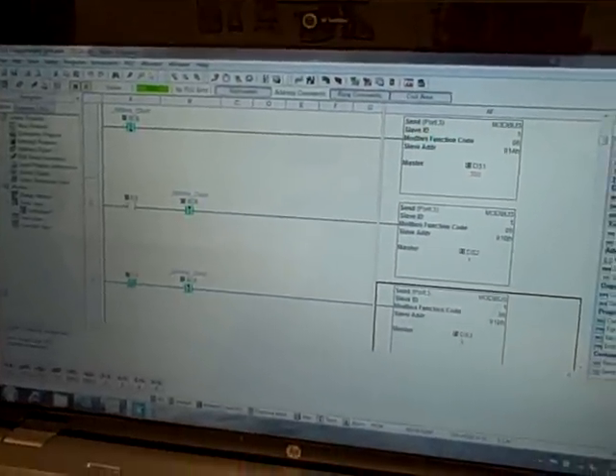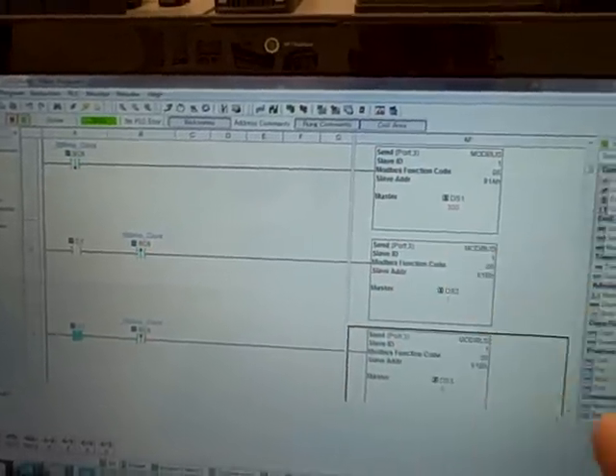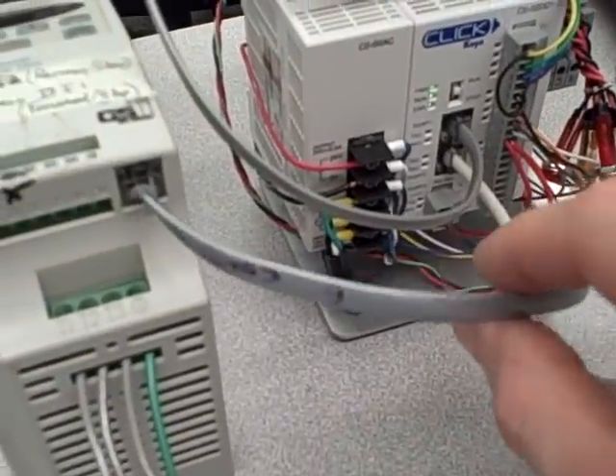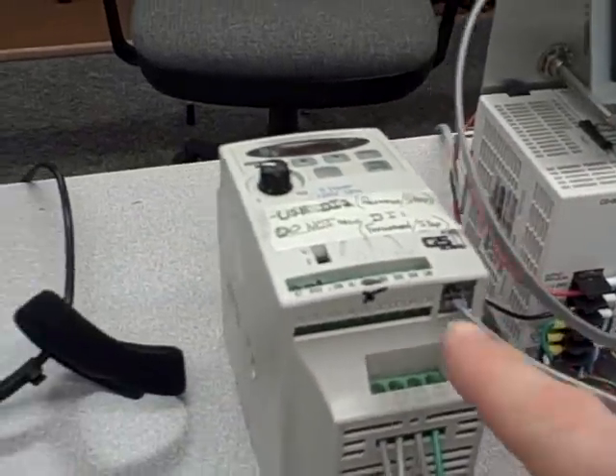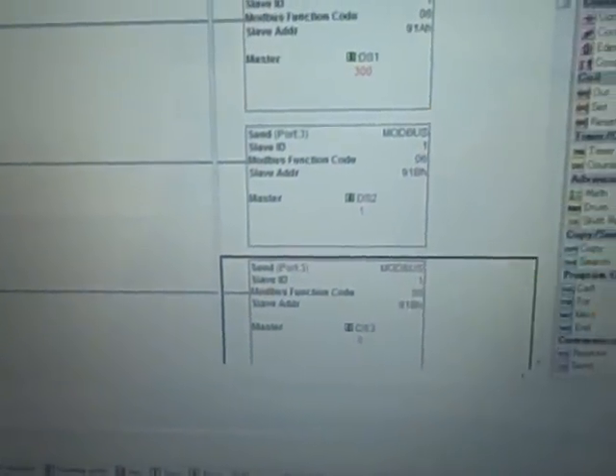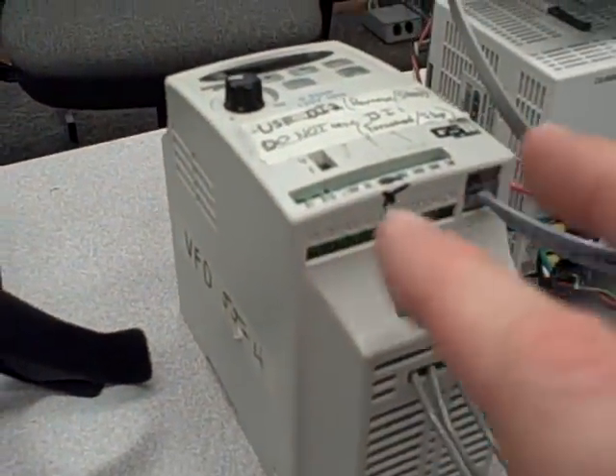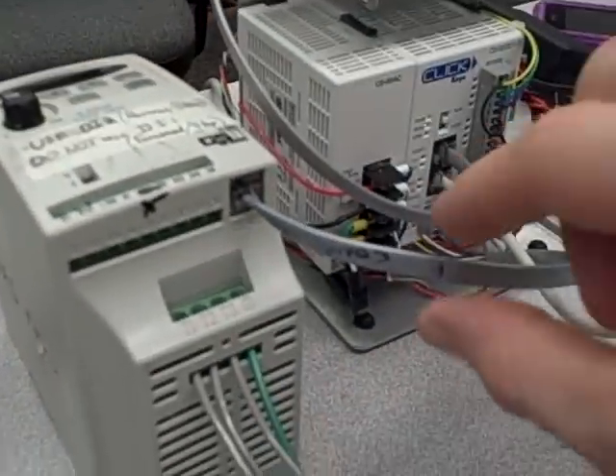So in a nutshell, that's our program. We're looking at control of the motor starting and stopping as well as speed control using a fixed-point integer value, and that's all being done over Modbus. This is very powerful because we could daisy-chain multiple Modbus devices on the same pair of wires and have the PLC address them separately simply by using different slave ID values and different communication instructions in the program. We could have over 100 different devices daisy-chained, all talking Modbus on the same pair of wires — highly efficient from the perspective of wiring.